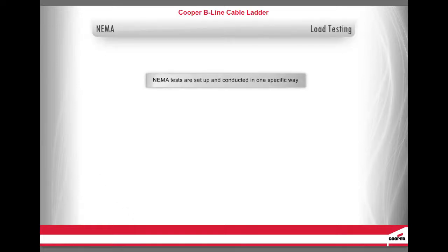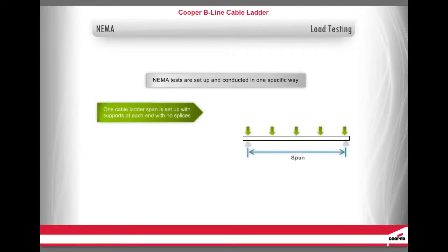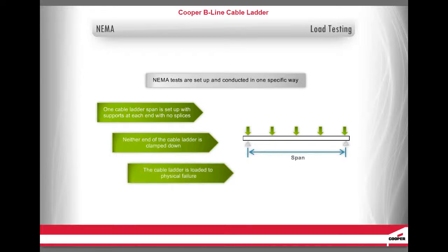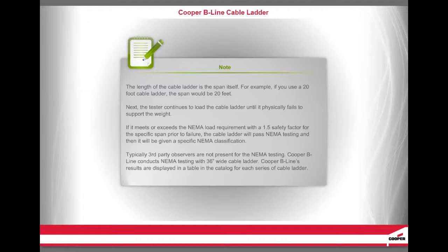The NEMA tests are set up and conducted in one specific way. One cable ladder span is set up with supports at each end with no splices. Neither end of the cable ladder is clamped down. The cable ladder is loaded to physical failure. The length of the cable ladder is the span itself. For example, if you use a 20-foot cable ladder, the span would be 20 feet. The tester continues to load the cable ladder until it physically fails to support the weight. If it meets or exceeds the NEMA load requirement with a 1.5 safety factor for the specific span prior to failure, the cable ladder will pass NEMA testing and be given a specific NEMA classification.